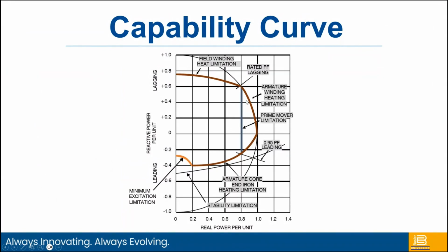This here is your armature winding heat limitation. So if you're producing too much current from the machine, you can basically overcurrent your machine and have the end iron overheating. And then at the bottom portion, this is where we would set up our under excitation limiter, so you're not reaching the end iron heating for your armature core. And beyond that is the steady state stability limitation. So you definitely don't want to fall out of synchronism between the rotor and your stator. So you set up the UEL to help protect you on this area down here at the bottom.